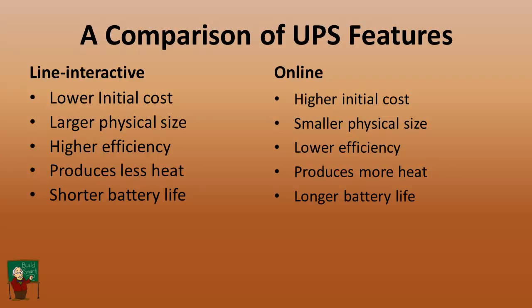However, since the line interactive has not quite the range of input voltages that it can handle, typically the line interactive might go from 90 to 140 volts that it can regulate the power and still produce, say, a nominal 120 if it were operating normally at that range. And the online may go as low as 60 and up to 150, 160. There are fewer circumstances for the online to actually be going into batteries. And so batteries are under less stress, so typically there's longer battery life on the online, and that can actually make up totally for the difference in the initial cost. As we said, the line interactive would spend more time on the battery than the online.